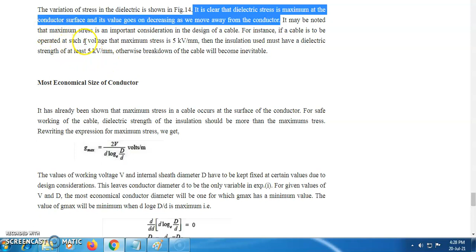It may be noted that maximum stress is important in the design of the cable. For instance, if the cable is to operate at a voltage such that maximum stress is 5 kilovolt per millimeter, then the insulation used must have a dielectric strength of at least 5 kilovolt per millimeter. Otherwise, the breakdown of the cable will become inevitable.